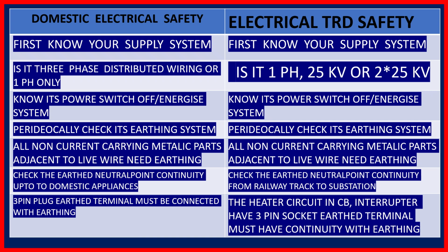All non-current carrying metallic parts, which are connected with the live system, and the cover and everything, are non-current carrying. It is metallic, like a water heater. Its body is steel made, but it is connected with the 3-pin plug earth point. So if your insulation fails, the supply will come to this metallic portion and to the earth. But if it is discontinued from your 3-pin plug earth terminal, you will get a shock.